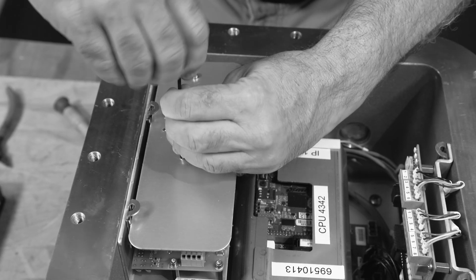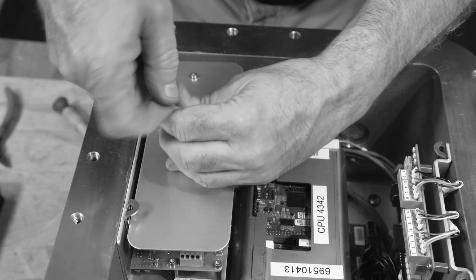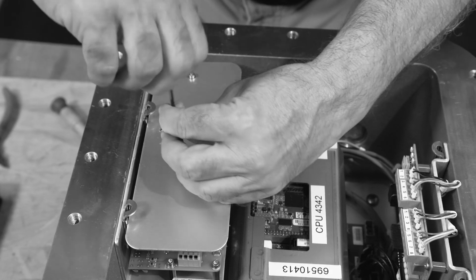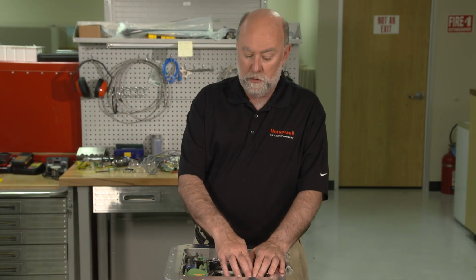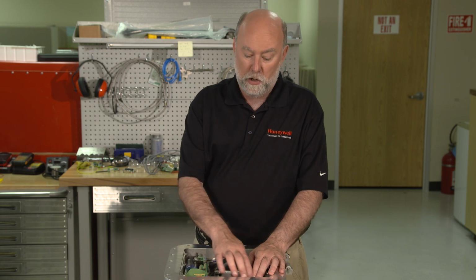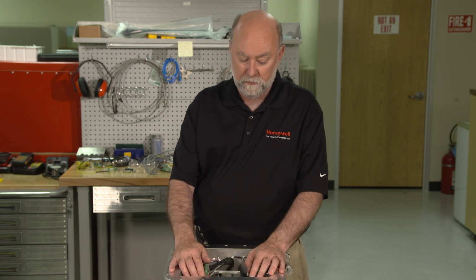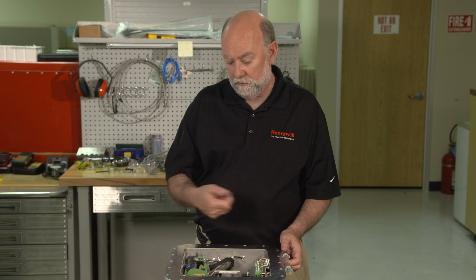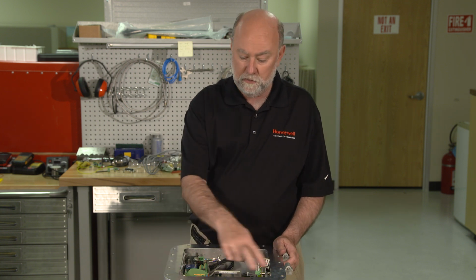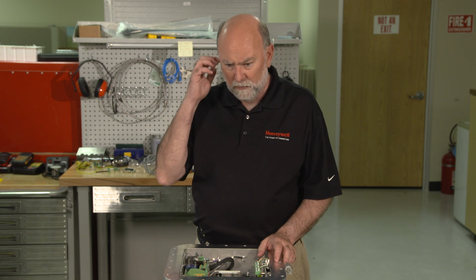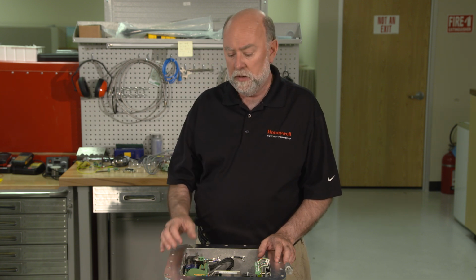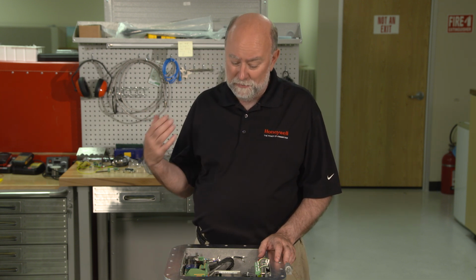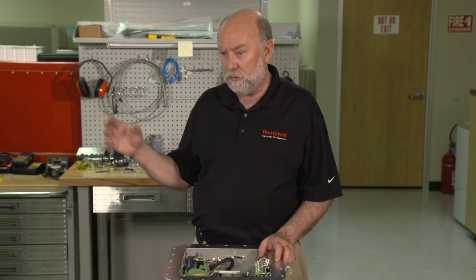Once we've reinstalled the cover plate onto the field terminal board with the screws that were supplied with the kit, we can proceed to terminate the customer's wires along the terminal blocks on the DIN rail here. Once we've done that, we can close the door to the explosion-proof box, bolt it down, re-energize the electronics. At that point, the next step will be to connect by Ethernet to this electronics with a laptop.